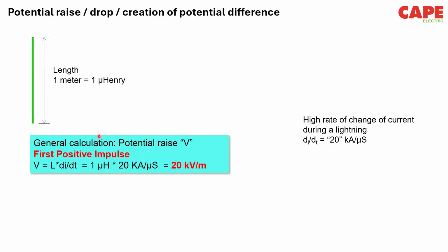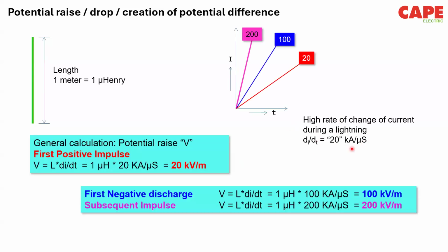And for a first positive impulse, the voltage drop across this wire length is inductance multiplied by di/dt, which makes the value 20 kV per meter. That means the voltage drop across this line is 20 kV per meter. Okay, di/dt is assumed as 20 kA per microsecond, which is given in part 1 of the standard. This is for a positive lightning strike. For negative and subsequent, it is 100 kA per microsecond and 200 kA per microsecond. So you can see here.